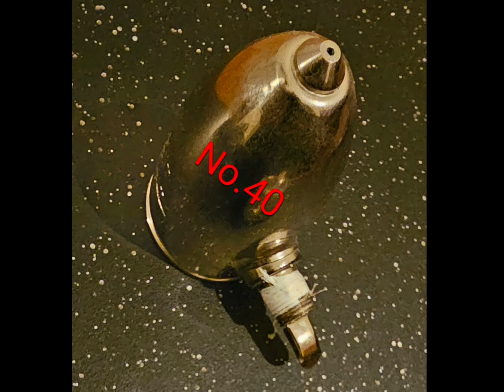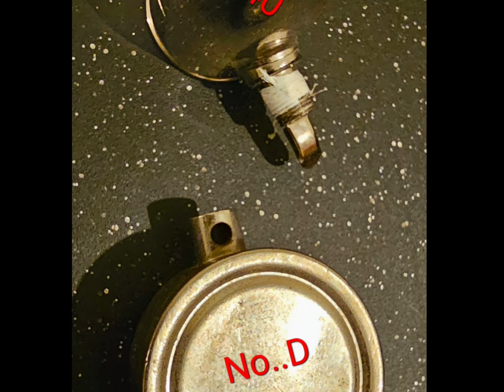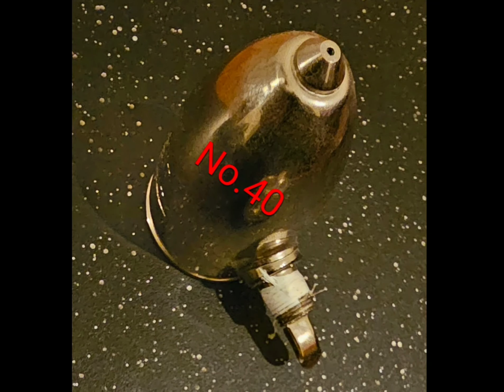No. And here's what I'm going to tell you. You would figure with the radiators in the lobby having the larger service valve openings that these radiators would heat up faster. They didn't. They heated up at the same pace as every other radiator. Because on those radiators, even if I decided to slap a Gorton D air vent on these things, they still heated up at the same pace. The steam got into the radiator faster, but it didn't heat up any faster as far as the overall output of the radiator. It took the same amount of time.